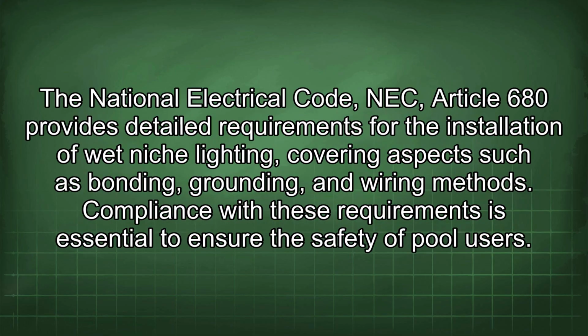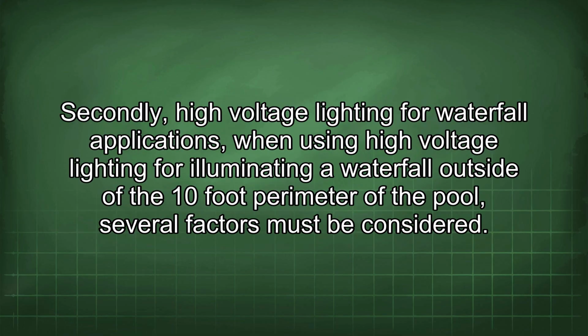The National Electrical Code, NEC, Article 680 provides detailed requirements for the installation of wet niche lighting, covering aspects such as bonding, grounding, and wiring methods. Compliance with these requirements is essential to ensure the safety of pool users. Secondly, high voltage lighting for waterfall applications. When using high voltage lighting for illuminating a waterfall outside of the 10-foot perimeter of the pool, several factors must be considered.